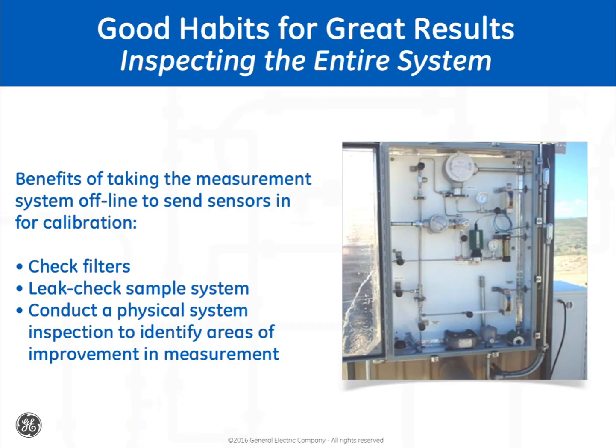The customer stories above give good examples of why a regular calibration program yields the most accurate measurement, enables the ability to properly identify the root cause and performance issues, current or pending, and builds confidence in the measurement system. For technologies such as aluminum oxide, removing the sensor and sending it back to the vendor for a calibration provides significant benefits. The sensor is cleaned and recalibrated in the same system that performed its initial calibration. Unlike in situ verification and third-party calibration, calibrations at the vendor's laboratory remove the moisture generation system as a variable in comparing past performance to present performance.